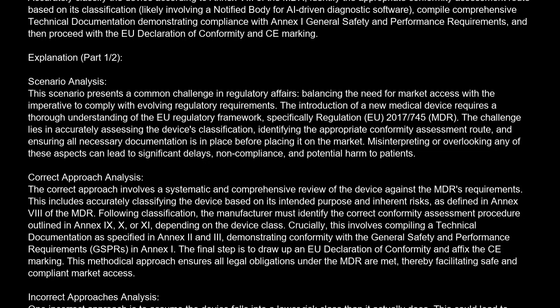The correct answer is B. Accurately classify the device according to Annex VIII of the MDR. Identify the appropriate conformity assessment route based on its classification, likely involving a notified body for AI-driven diagnostic software. Compile comprehensive technical documentation demonstrating compliance with Annex I general safety and performance requirements, and then proceed with the EU Declaration of Conformity and CE marking.